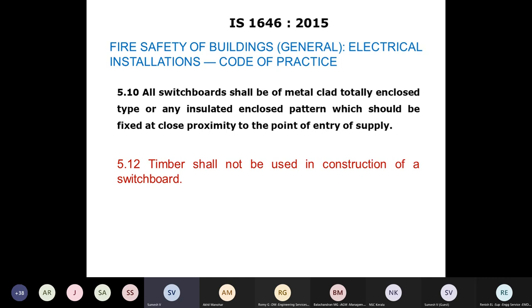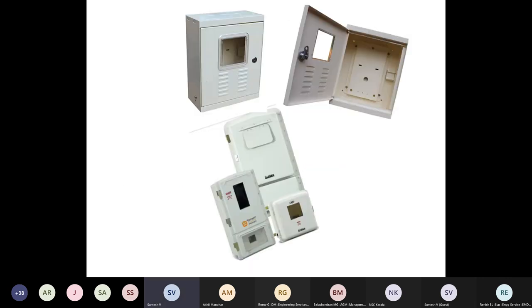Then clause 5.12 says that timber shall not be used for construction of an electric switchboard. A metallic switchboard is preferred for constructing the meter board. These types of meter boards are to be used. Here the meter is to be fixed inside that box, not on the hinged door.